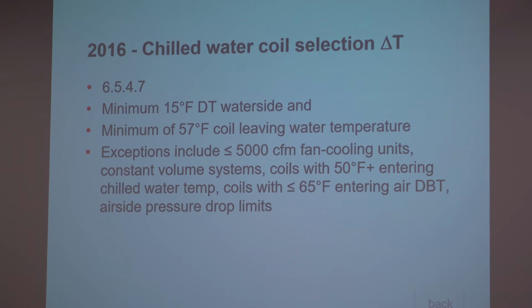So one of these, because I mentioned ASHRAE 90.1 is a design standard, so what we're trying to give you is not necessarily how to operate your buildings, but how to design your buildings so that they have a chance anyway, if you do it right, of operating very efficiently. And so one of the requirements that came up in the last code cycle that I was involved in at ASHRAE was this chilled water coil selection requirement.